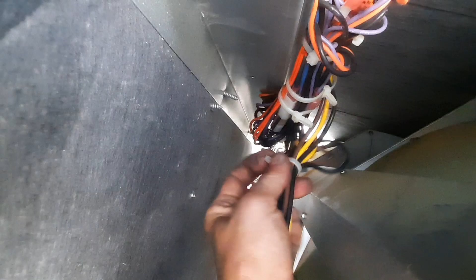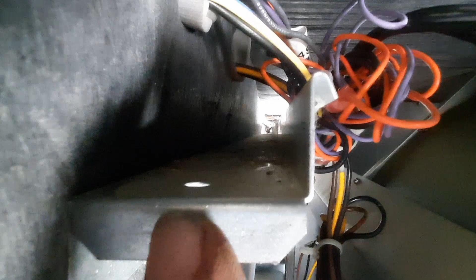If you pop these little wire ties out, they just poke in the bottom here. You can pull all of your wires out of there. You can see the jumble of wires that's in there. I don't see anything noticeable. And if I look down that trough, I don't see any black spots or anything like that. So I don't think I've lost a fan motor, or at least I haven't shorted a fan motor out directly. Now I do see some of these wires are labeled crankcase heater right there. So it's possible if it's fed from the same place.